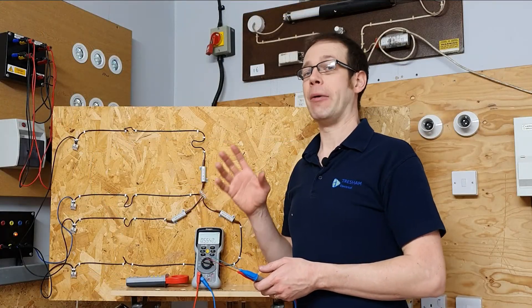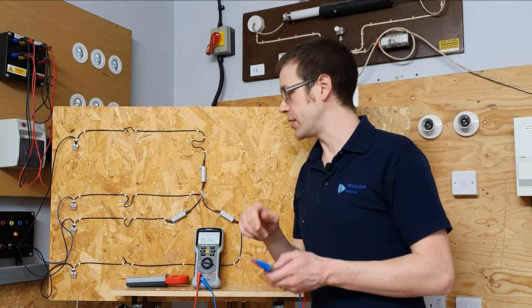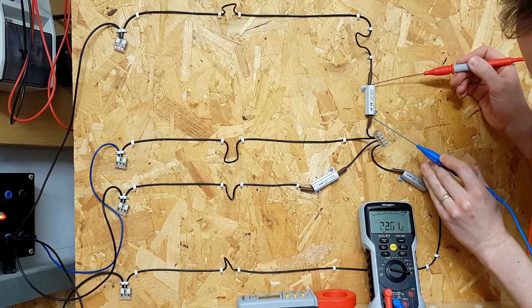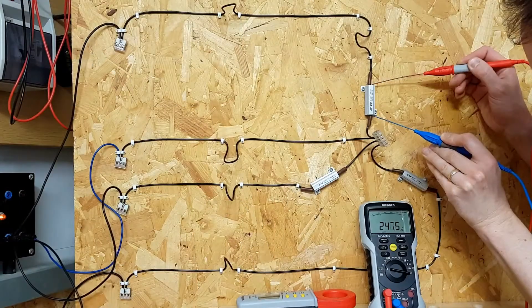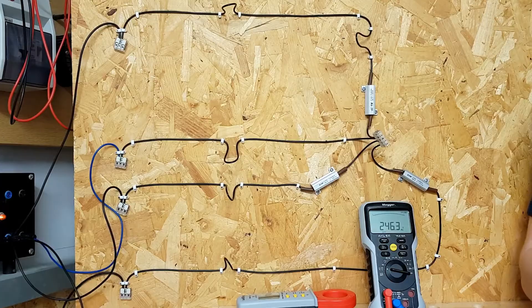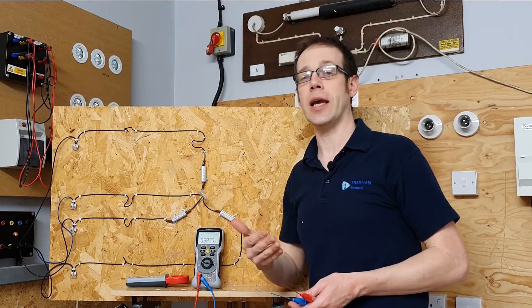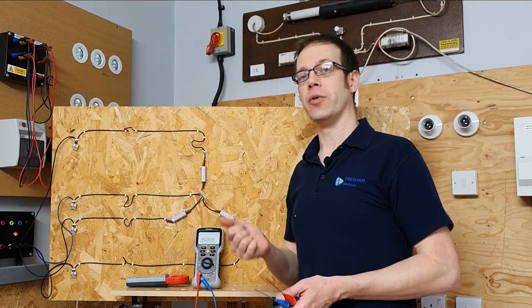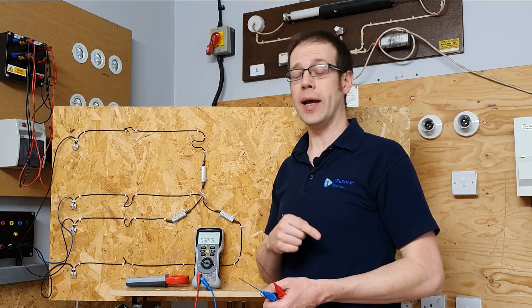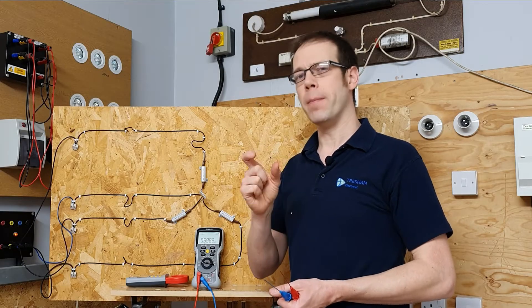Now we're going to measure our phase voltage — the voltage across the load. Connecting across the load here, you can see we've got 246.8 volts. Hopefully those values are familiar: in the UK our nominal voltages are 400 volts for three-phase and 230 volts for single-phase, and we're pretty close to those values. Let's go to the whiteboard to look at how those two voltages relate to each other.